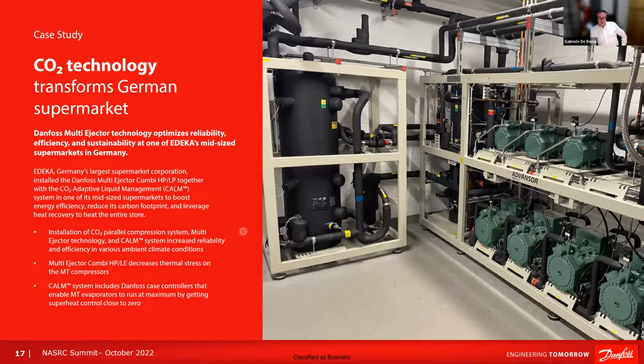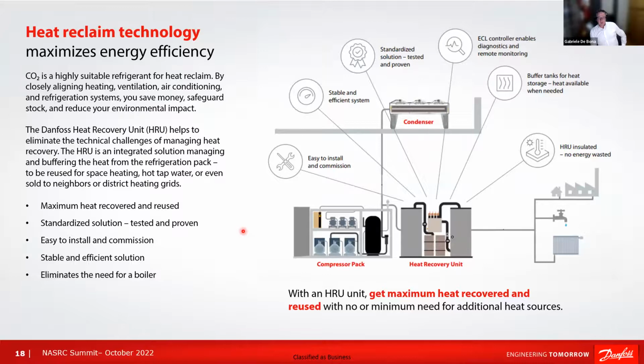So the installation of the CO2 with parallel compression, multi-ejector, and the CALM algorithm has increased the reliability and the efficiency of the system, and also has reduced the thermal stress on the compressor, reducing the need for servicing them. That can also be positive from a point of view of cost reduction.